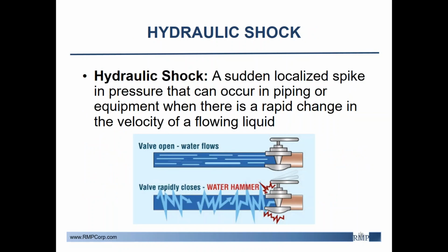The release was caused by hydraulic shock, which I'm sure many of you that work on these systems are well aware of. Hydraulic shock is a sudden localized spike in pressure when there's a rapid change in the velocity of a flowing liquid. This can occur within pipes, tanks, and especially at valve connections, and often happens when vapor and liquid are present together in a single line. Sudden changes in pressure and volume can cause catastrophic damage to piping and equipment.